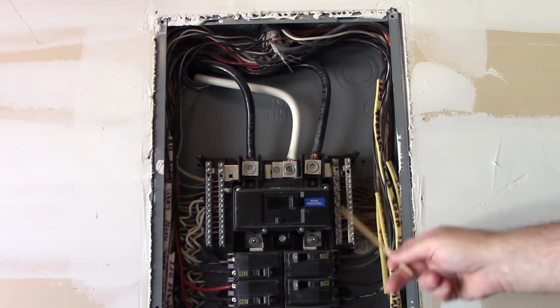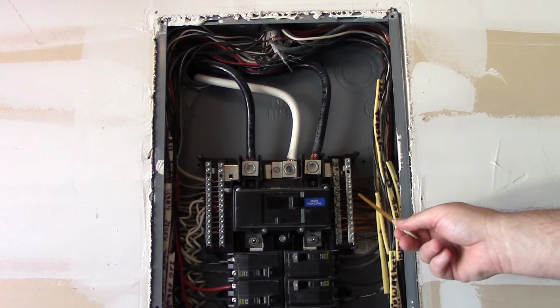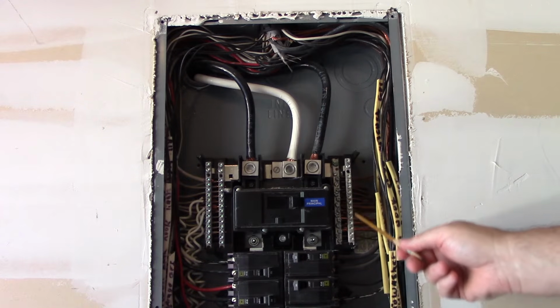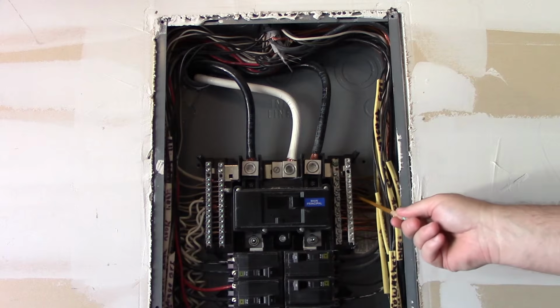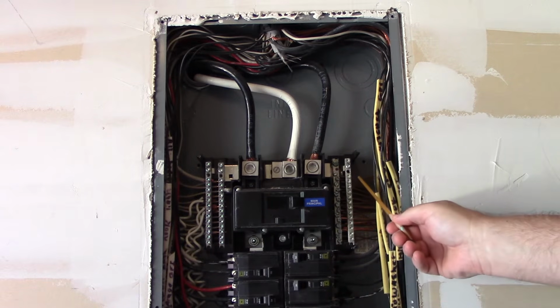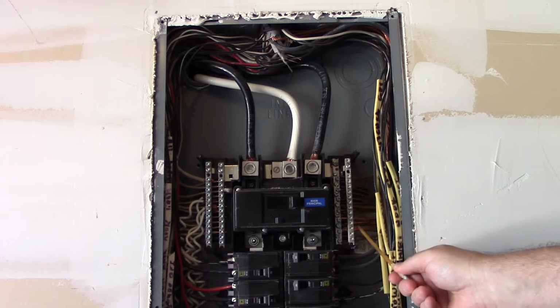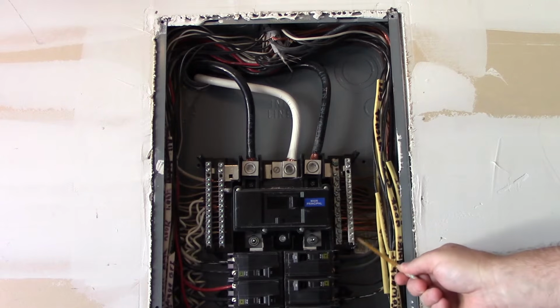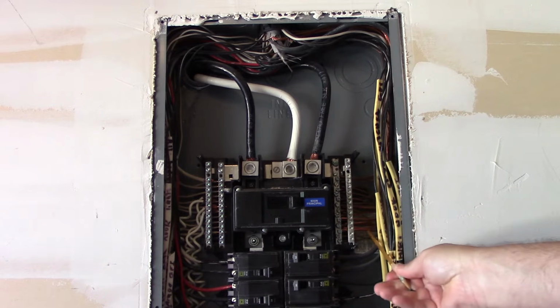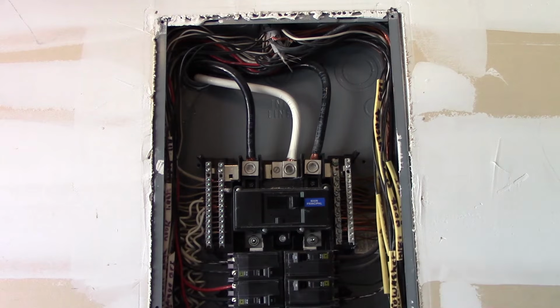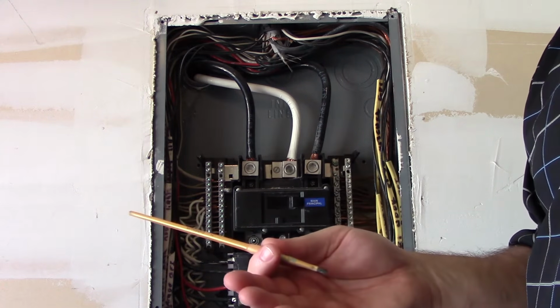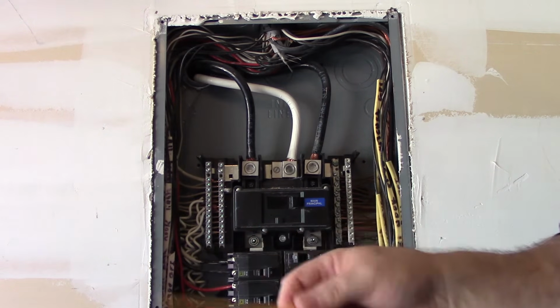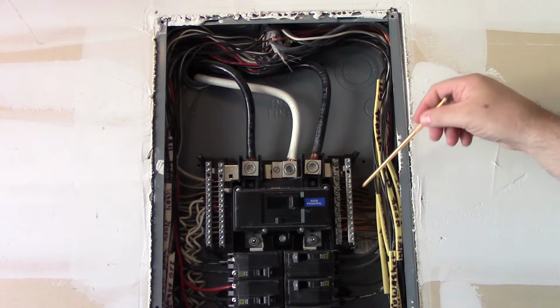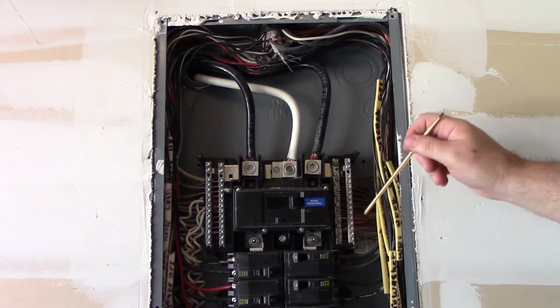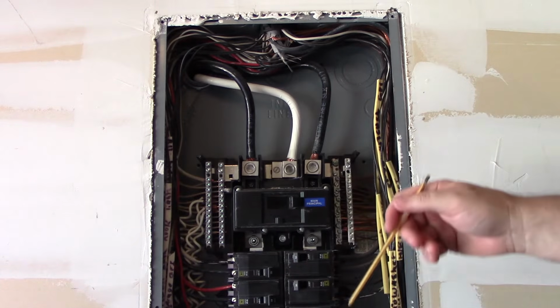Okay, so as we come down, we see these equipment grounded conductors. We want to make sure that each one of these equipment grounded conductors is terminated in a screw, and that none of them are loose. What I like to do with a non-conductive probe is move them down a little bit, and since it's non-conductive, I try to see if any of them wiggle around or move. Whether or not your standard of practice allows you to do that is up to you. If you can see all that from a visual inspection, good for you, but we're going to try to show you some of the things that I would look for.